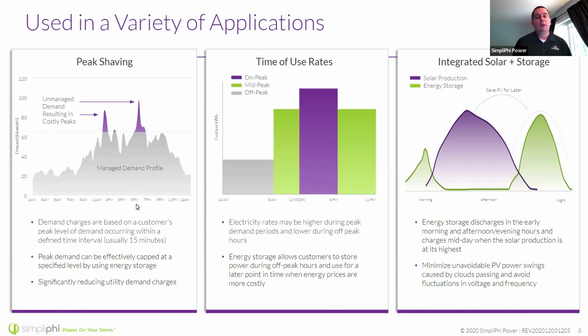One way to attack these costs is to use demand management, or peak shaving, where you've got batteries charging from solar or from the grid, and you tell your inverter to discharge those batteries before you hit that highest peak. In this instance, we've got a dotted line, and we're telling the inverter not to go above that, into the purple, therefore preventing that highest charge from occurring. So it's a great way, if you're on a demand rate schedule, to help curb some of the costs the utilities are throwing at you.